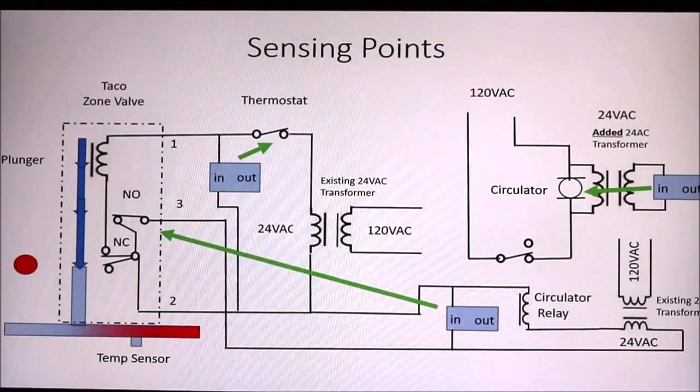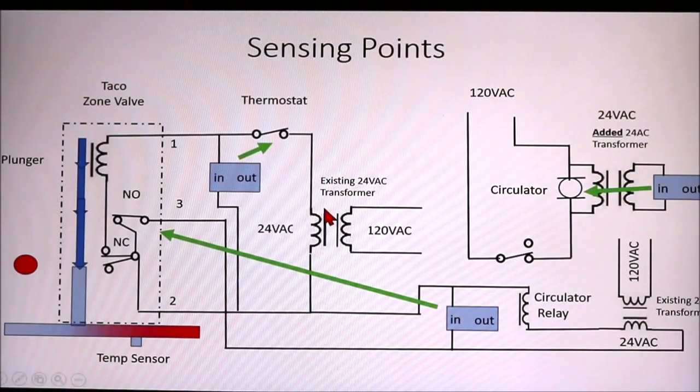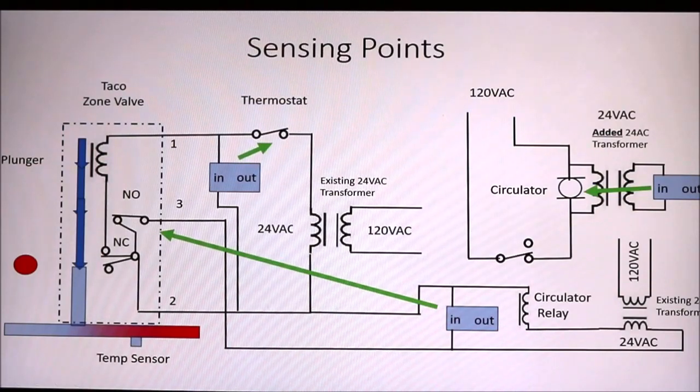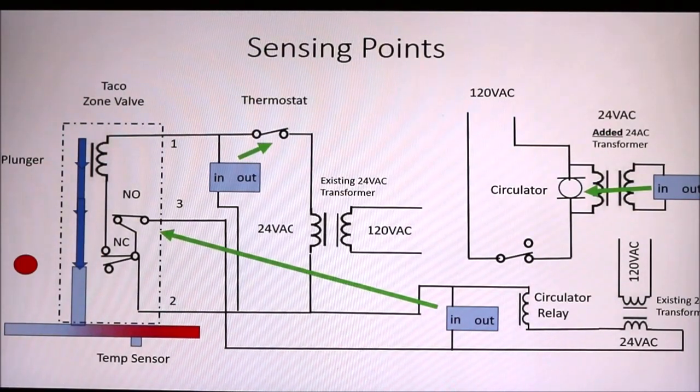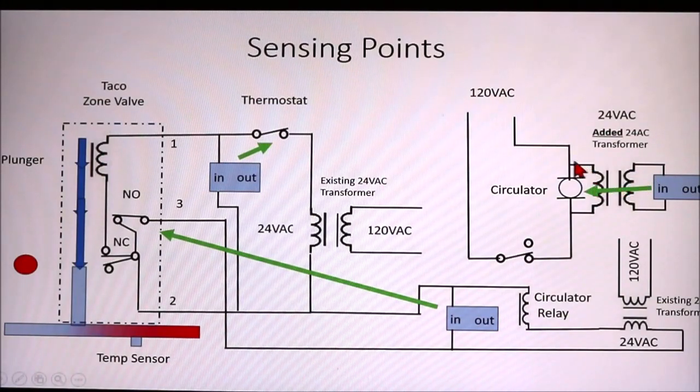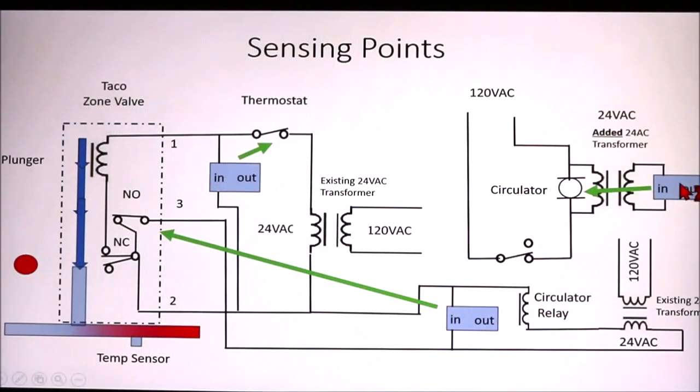Now, these transformers, the other transformers, as I mentioned, are existing transformers in your system. They're needed there, so they're fine. This one would have to be added. And 24 volt AC transformers are pretty common. They're anywhere from $10 to $15 a piece. So we'd hook one up across the circulator. So when the circulator is seeing 120 volts, it would go through that circuit I showed you earlier and put out a voltage to show that the circulator is working.